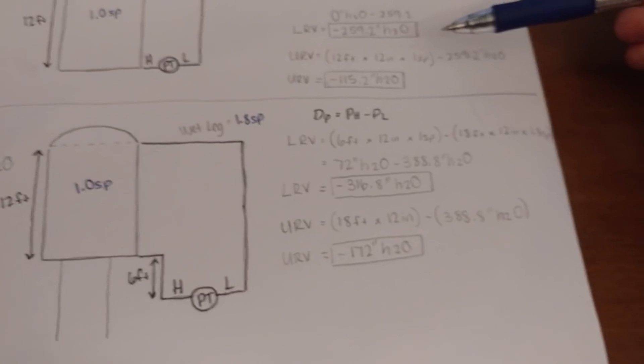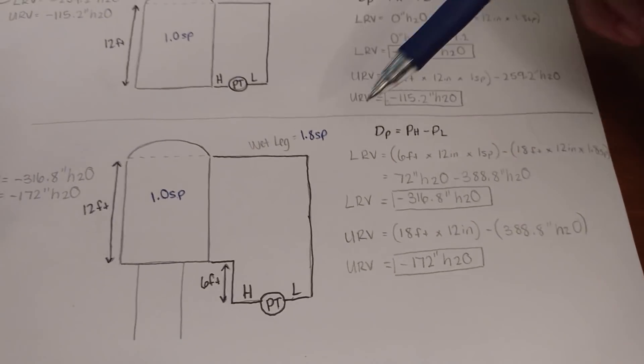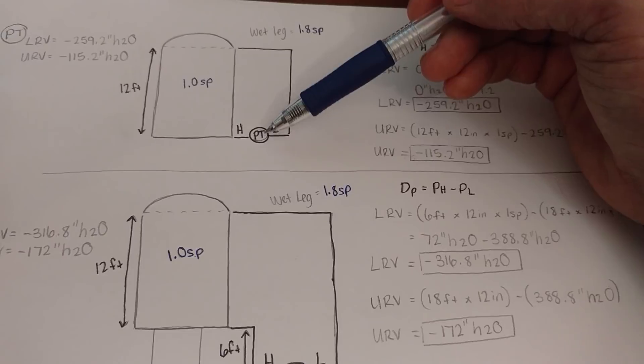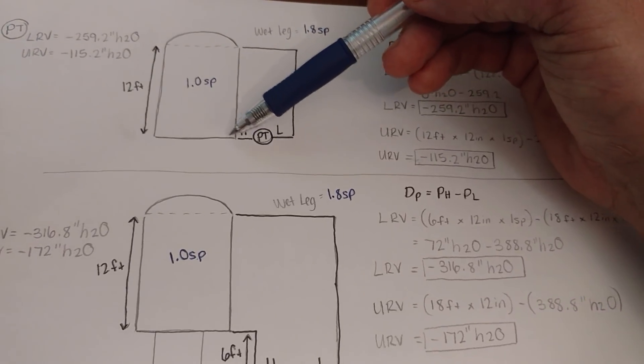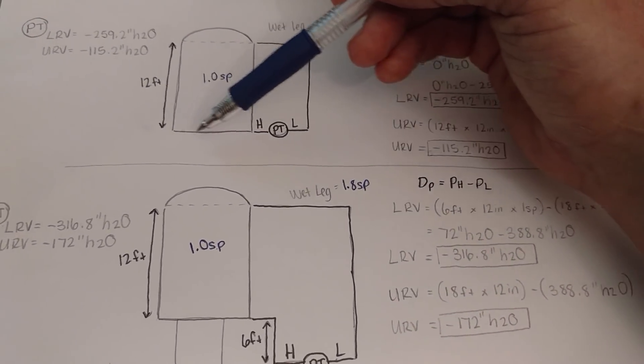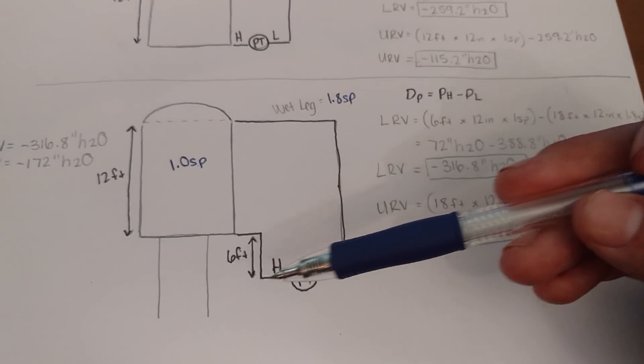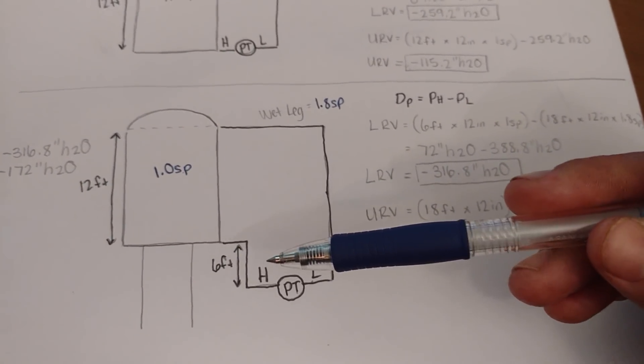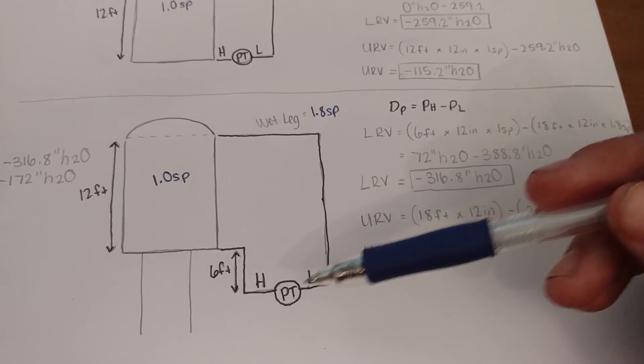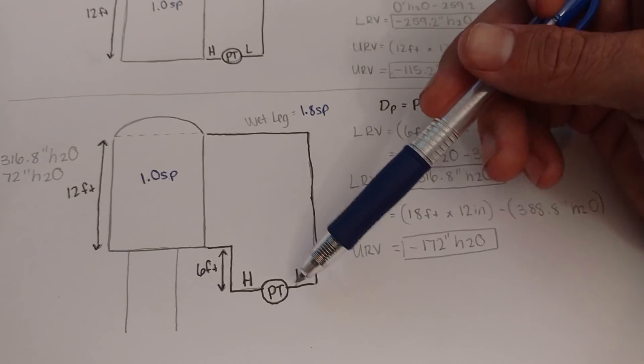We're going to use the same formula: differential pressure equals pressure high minus pressure low. For the lower range value in this situation, the pressure high side is not going to be zero, because it's not flush with the base of the tank — it's actually 6 feet below the tank. So we've got to find that hydrostatic pressure: 6 feet times 12 inches times the specific gravity of water (1), giving us 72 inches H₂O for our pressure high.